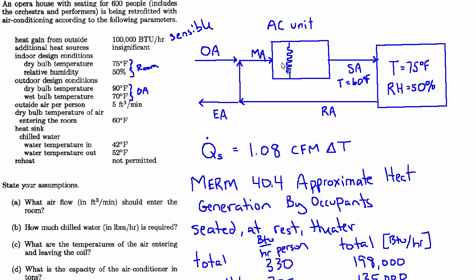So there's this mixed air condition, and that's what's hitting the coil. So we should be able to calculate what that mixed air temperature is, but we're going to need to know the relative volumes. So in the last part, we calculated that the supply air volume was 14,500. When we get around to here, there's going to be some exhaust. How much exhaust?